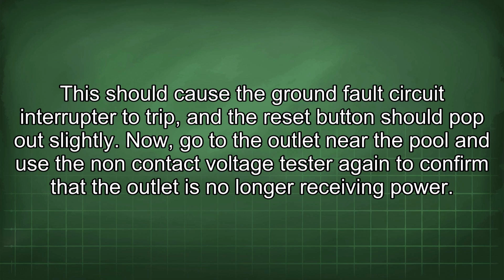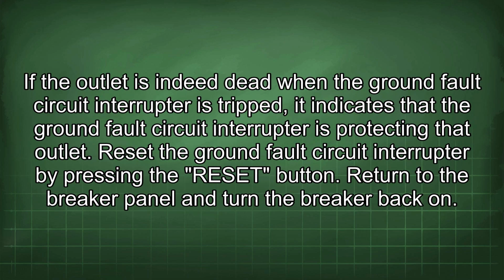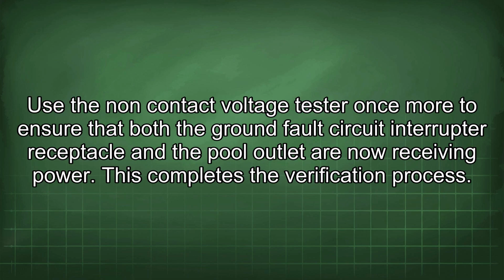Now go to the outlet near the pool and use the non-contact voltage tester again to confirm that the outlet is no longer receiving power. If the outlet is indeed dead when the ground fault circuit interrupter is tripped, it indicates that the ground fault circuit interrupter is protecting that outlet. Reset the ground fault circuit interrupter by pressing the reset button. Return to the breaker panel and turn the breaker back on. Use the non-contact voltage tester once more to ensure that both the ground fault circuit interrupter receptacle and the pool outlet are now receiving power. This completes the verification process.